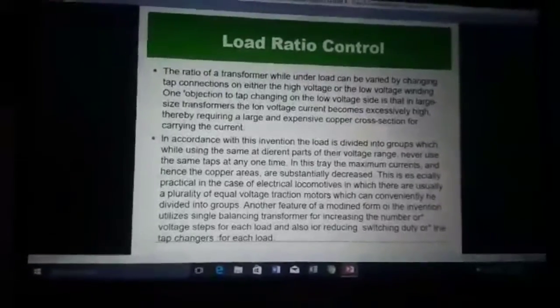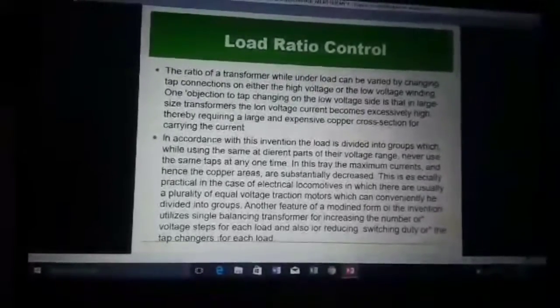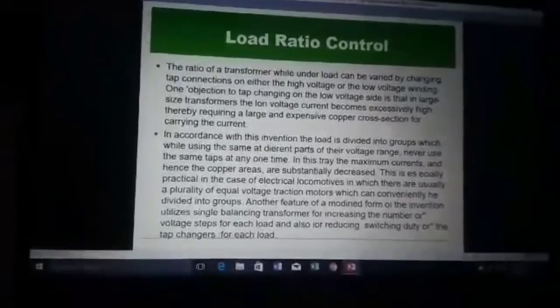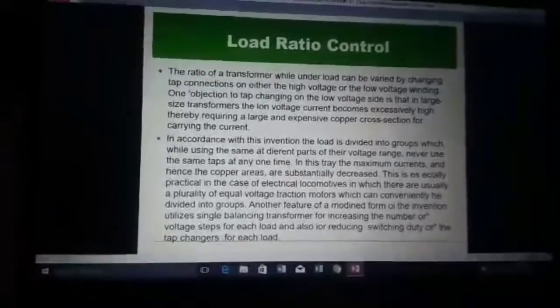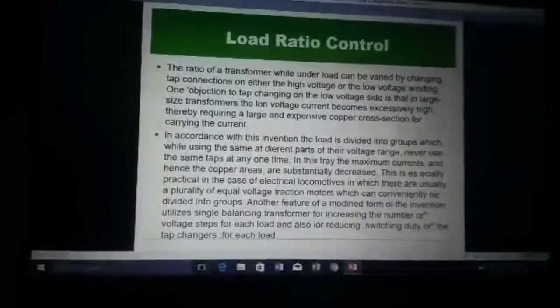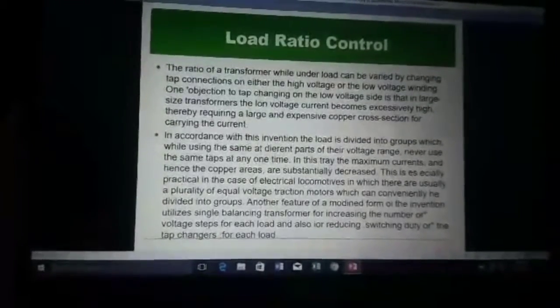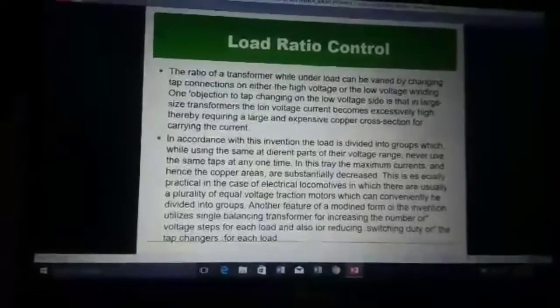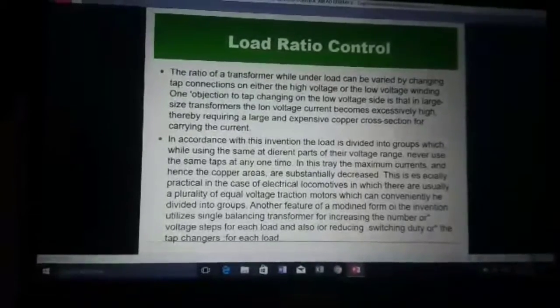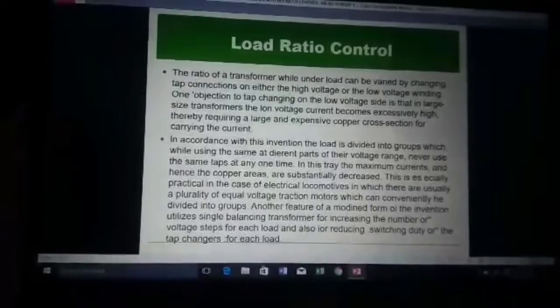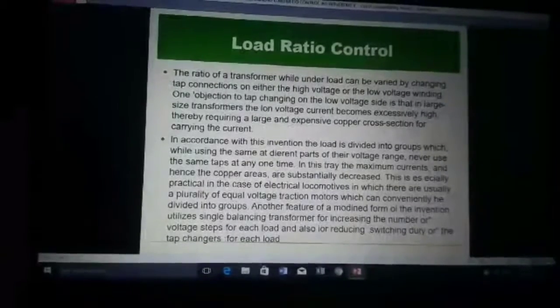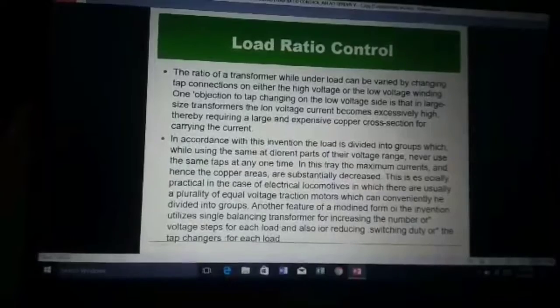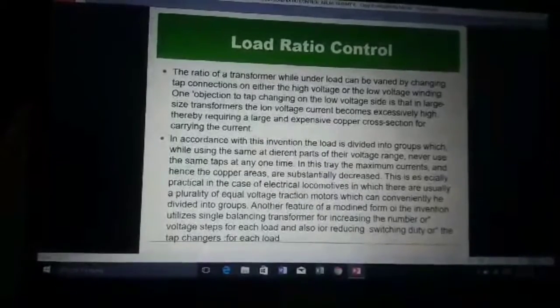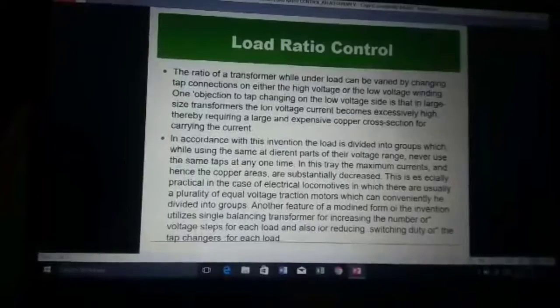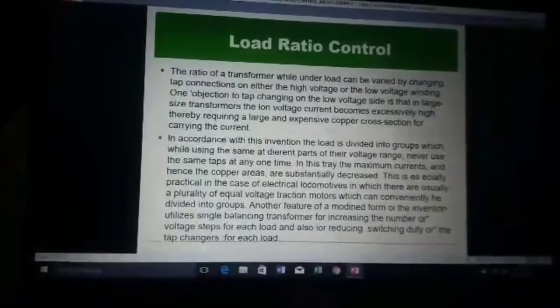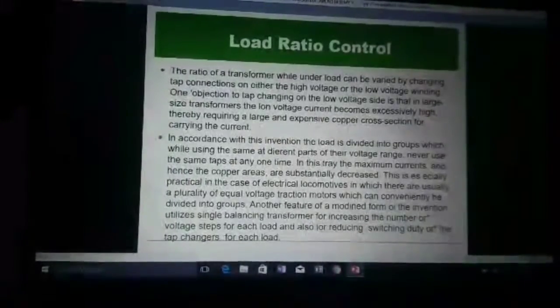In accordance with this invention, the load is divided into groups which, while using the same or different parts of their voltage range, never use the same taps at any one time. In this way, the maximum currents and hence the copper areas are substantially decreased. This is especially practical in the case of electric locomotives, in which there are usually a plurality of equal voltage traction motors which can conveniently be divided into groups.